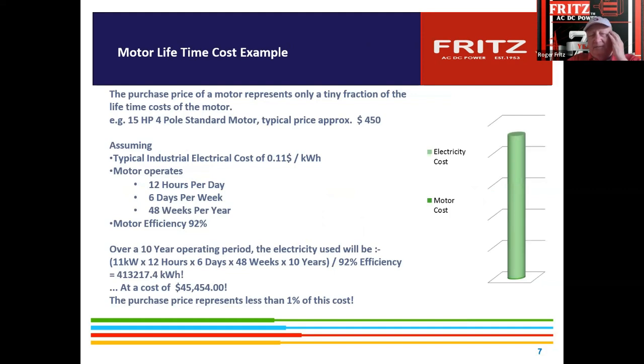This slide's a little bit dated, but an example is a 15 horsepower motor that cost $450. Now it's almost $750, $800. But if it ran 12 hours a day, 6 days a week, 48 weeks a year, back even at 11 cents a kilowatt-hour, and a lot of times we're now sitting at almost 22 cents, over 10 years that equated to the motor using $45,000 worth of power. Now it's more around 70 or 80,000.